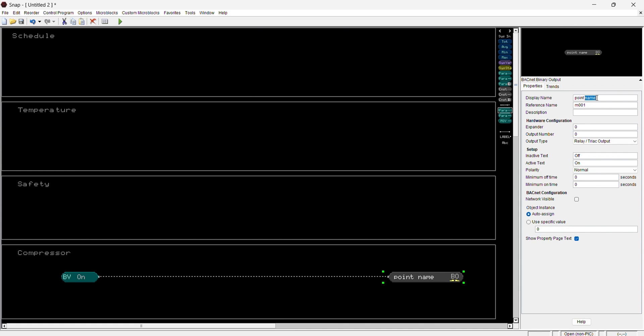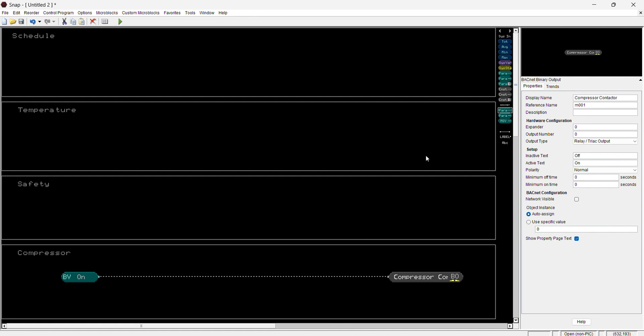I'm basically sending an ON signal to my contactor coil — and we can label this 'Compressor Contactor.' Can I simply send an ON signal here? Yes, I can, but that contactor coil would be receiving 24 volts all the time, 24/7, and we don't want that. So I could technically do this, but that's not a good program.